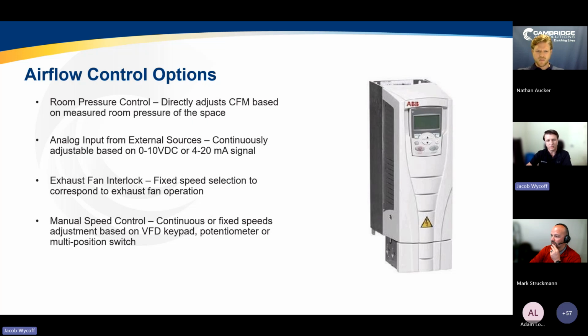And then manual speed control is a great option if the unit does not call for variable speed today, but you want some flexibility in the future. You want the ability to test and balance the unit, and you want some flexibility in the future to maybe add some filtration. Maybe you remove a weld booth in the future and you want to decrease the CFM slightly. Having some variable speed options, even as manual speed control, can be great to provide the user some flexibility.